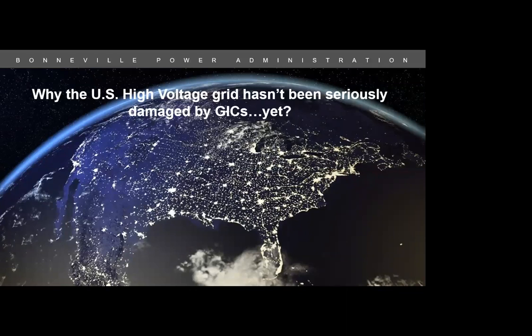There were 3 magnetic storms between 1964 and 1986 that didn't appear to cause damage, at a time when the grid was less integrated than now. However, an intense solar storm on March 13th of '89 caused excessive overheating of a series of connections in an Arizona Public Service shell-form transformer, gassing of a number of transformers in the northeastern US and Canada, and several failed capacitor banks. The system has grown significantly and is therefore more vulnerable to these induced currents, so there is heightened awareness to manage and mitigate this risk.